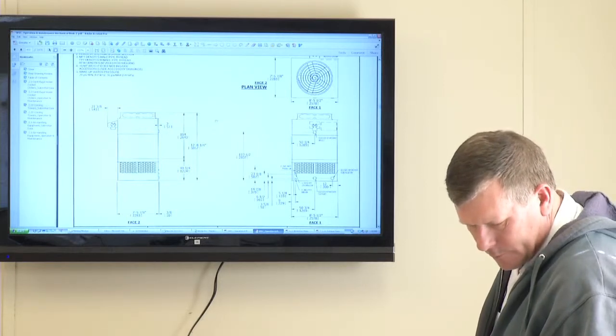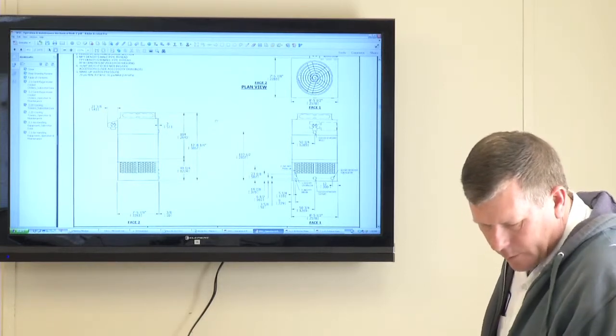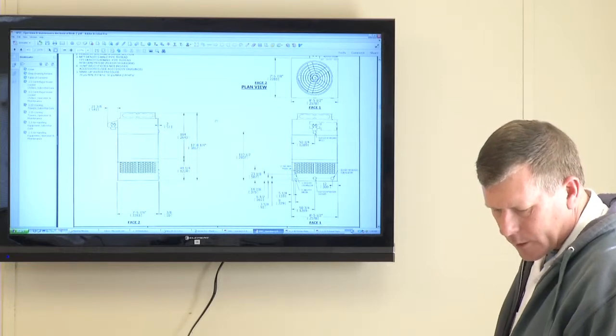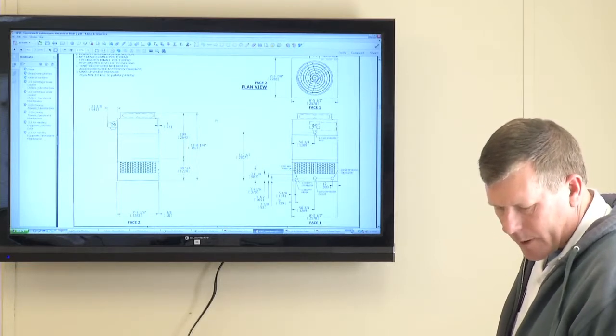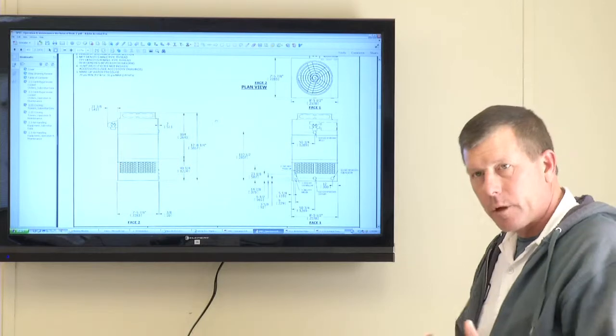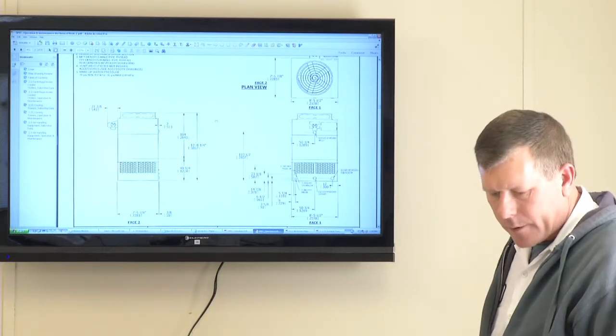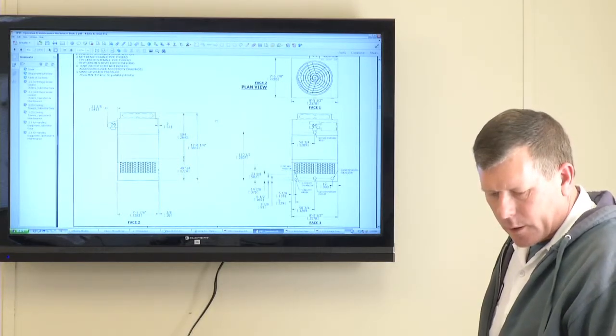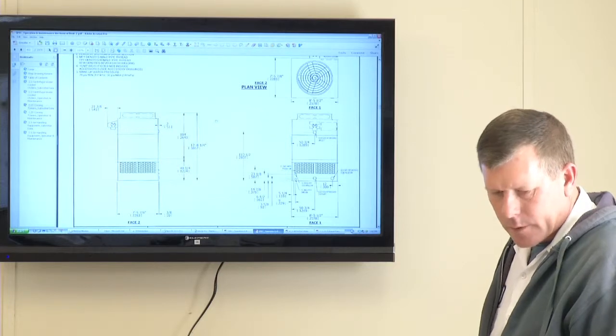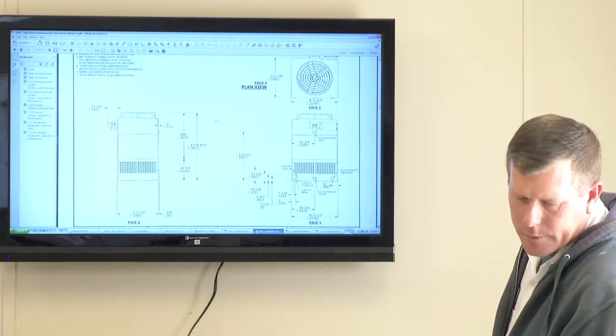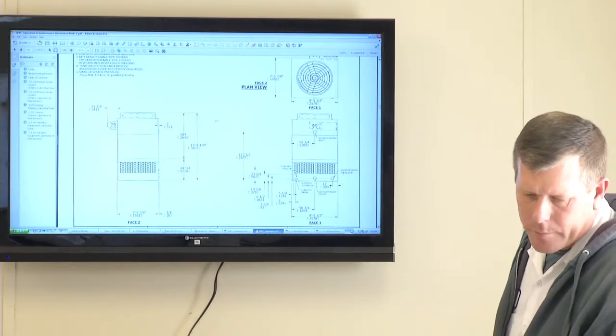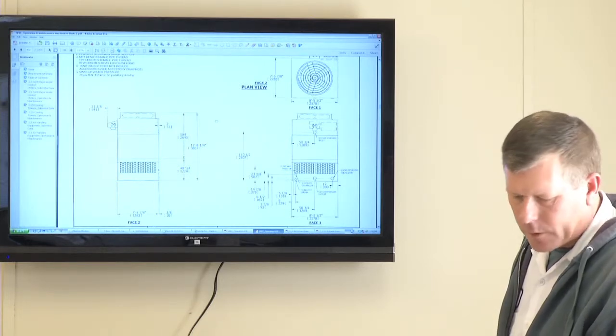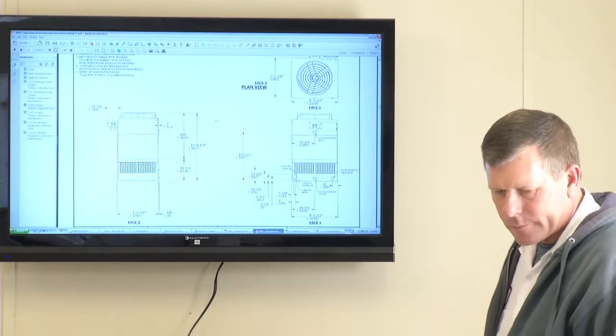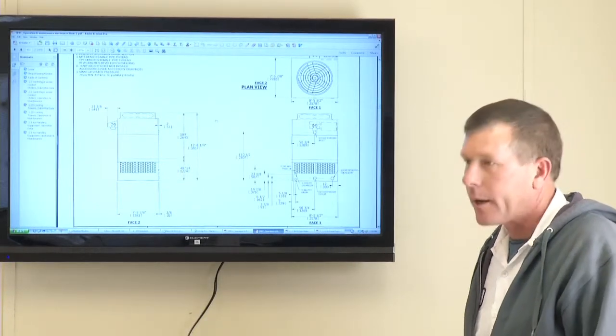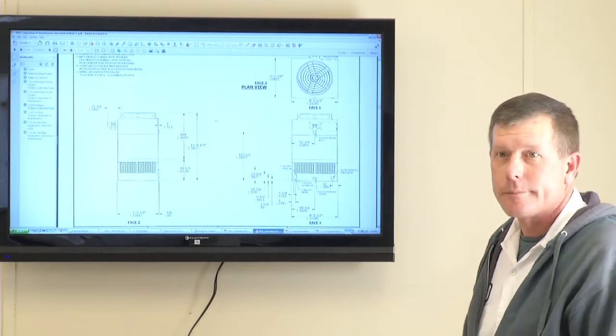And as far as the safety cutoffs, we have low water cutoffs in the basin. There's nothing electronic, and we have manual floats, brass floats, plastic floats with the brass fill, pretty standard. There's nothing else there. There's a low water cutoff for the basin heater, and it's either a 4 to 6 kW heater. I'm not exactly sure. Both of them operate the same, and of course they have a low water cutoff in that. So that's pretty much it. Are there any questions?